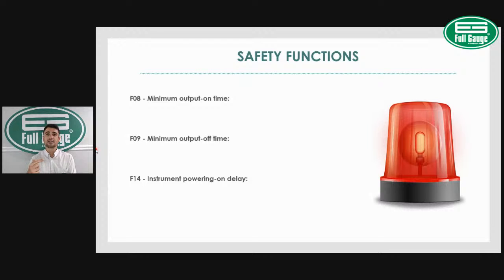So it's likely that my compressor will be going on and off constantly. In order to avoid that constant switching, you can actually set a minimum output on time and off time. So regardless of the temperature that it reaches, it will first respect the time. Again, to prevent compressor short cycles.